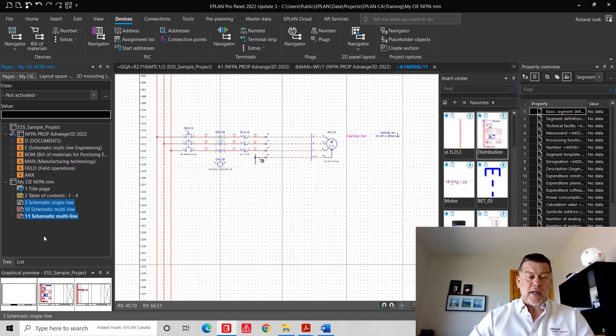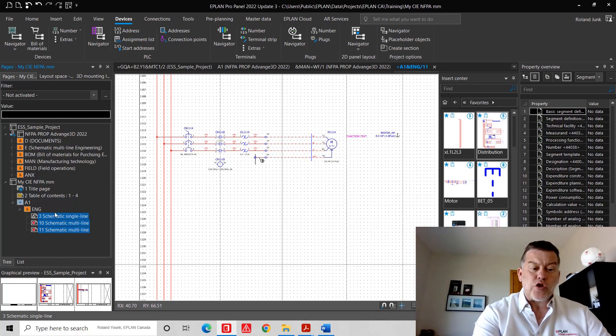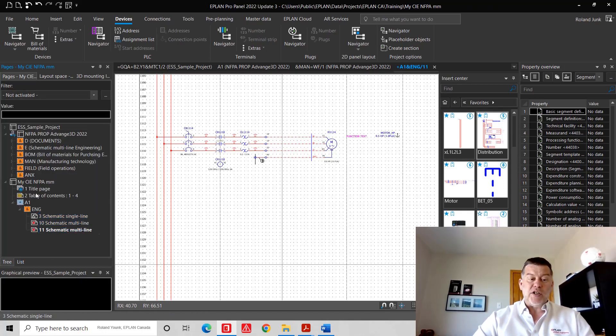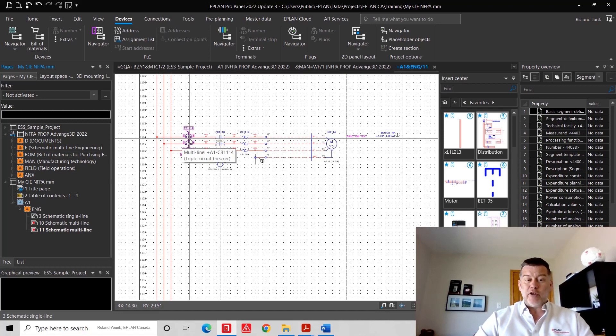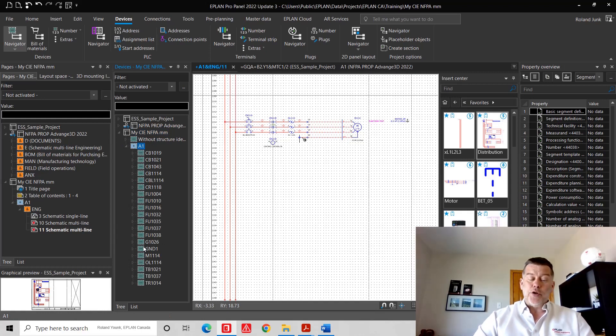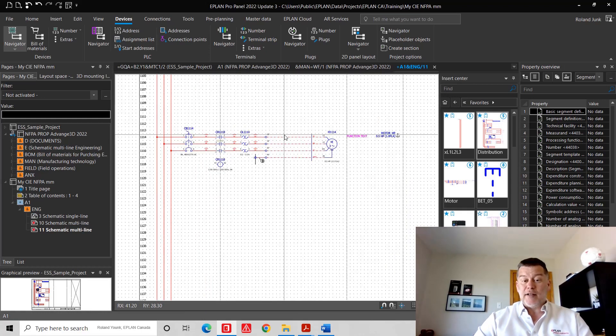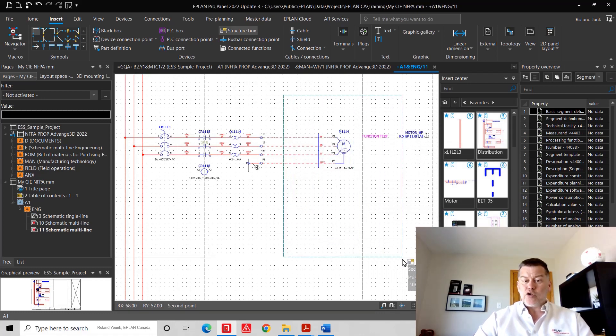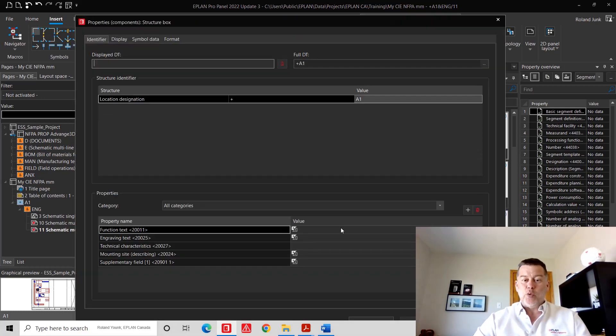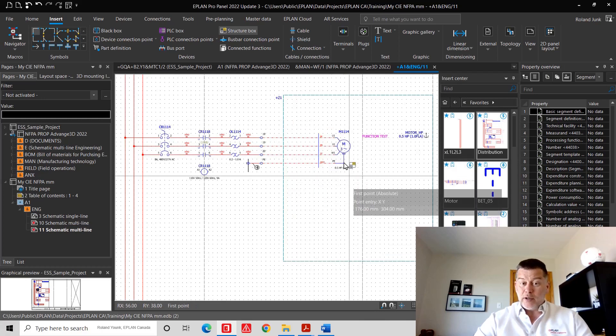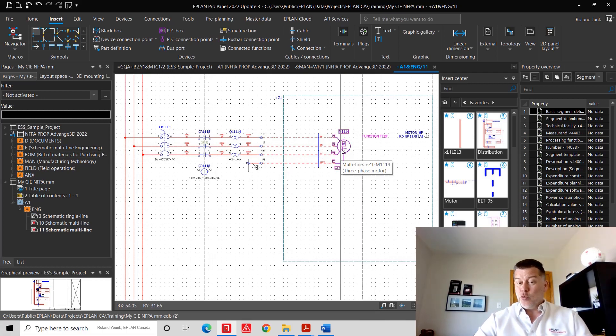Omitting the functional designation for now, this creates a kind of folder structure — not exactly folders, but a tree view display. In list view you won't see it; it's purely a display method. Interestingly, every component is now assigned to that location, and in the navigator I can see all devices assigned to enclosure A1. Of course the motor should be out in the field, so I use a structure box — an area inside the page I redefine to a different location, something like Z1 for zone one. This reorganizes all objects inside that area to now belong to Z1, a new location.